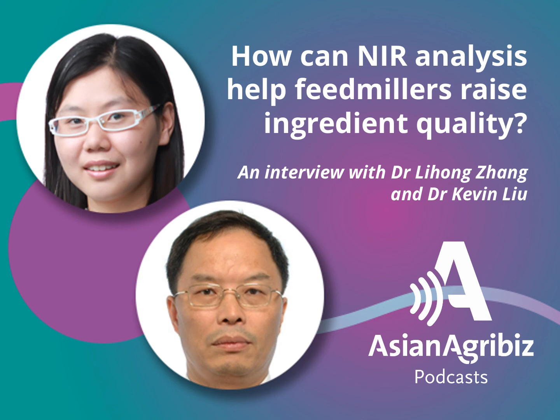Yes, we have seen the evolution of NIR instruments from the early grating instruments that require very strict working conditions to more robust FT-NIR and lately portable units. We believe the application of portable units is very limited to very basic parameters due to their detection capacity and spectra transmission stability. With future development, I assume a hand-sized device with more accurate calibrations is possible and could be used in the field to check advanced parameters of raw materials.